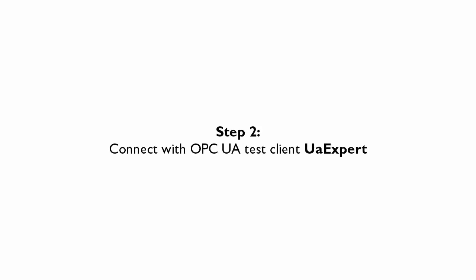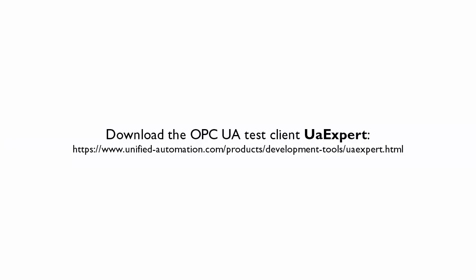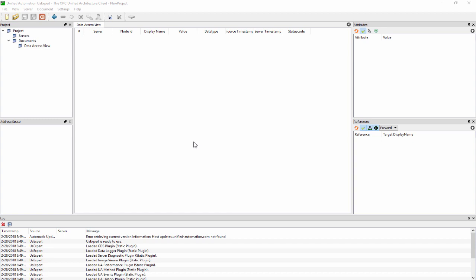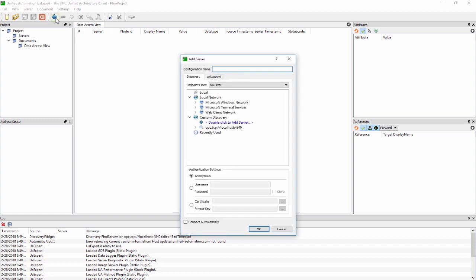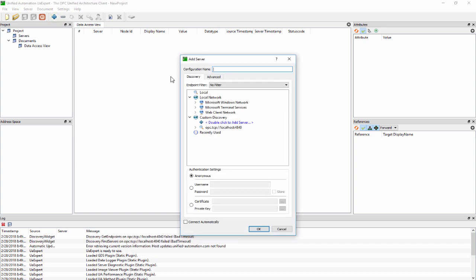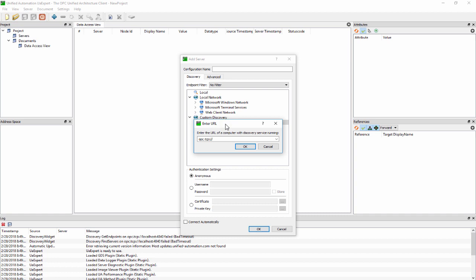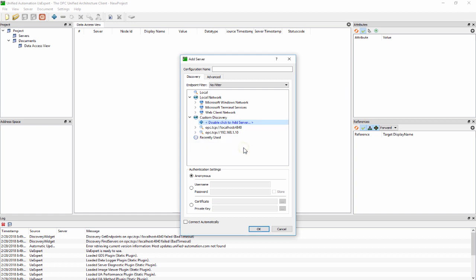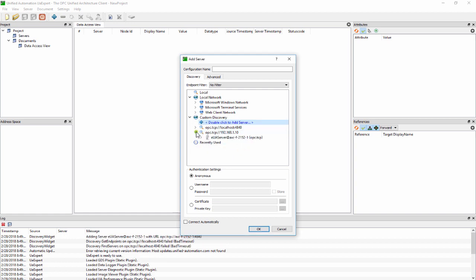We will now test the OPC UA server function using UAexpert software from Unified Automation. In UAexpert, add a new server. Enter the IP address of the connected PLC. Use the discovery service to select one of the available security policies.